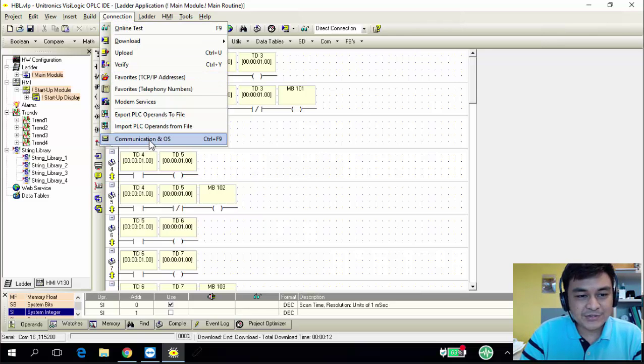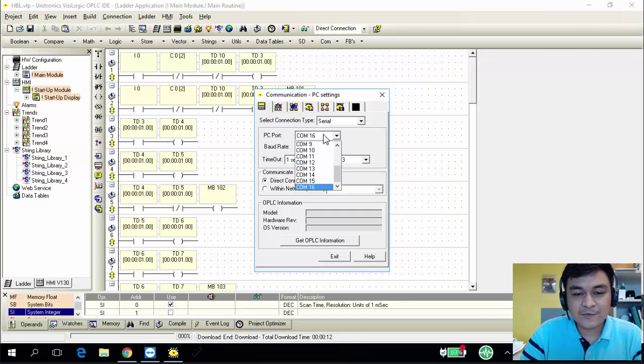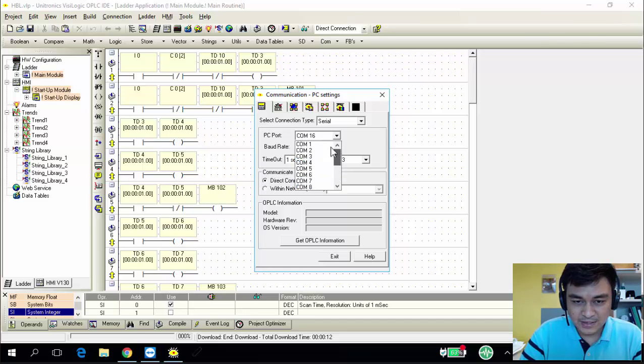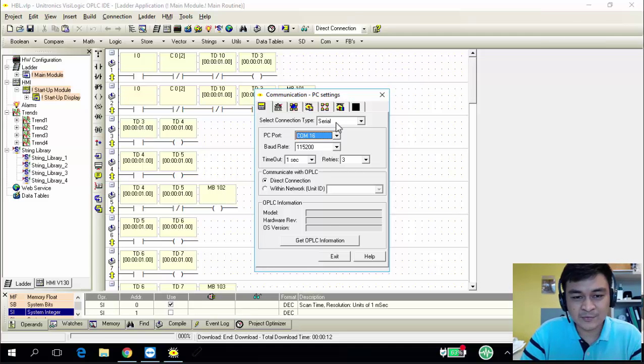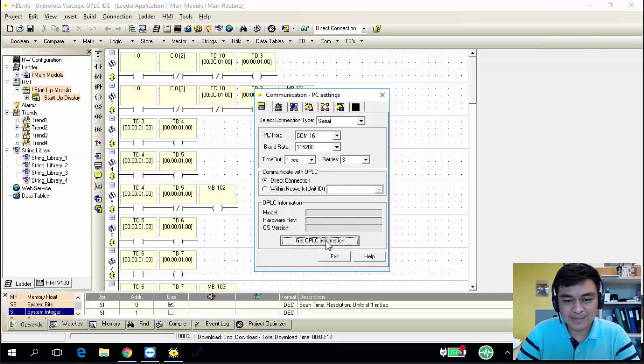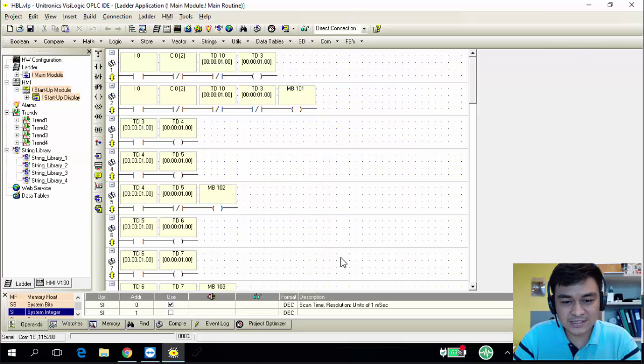Go to Connections, then Communication and OS. For the lab, we are using COM1. For my PC, I'm using COM16 — so there's a slight difference. The baud rate is 115200. We use serial communications. Please check your communications and make sure you can see the OS version, which means your PC is connected to the PLC. After that, just click Exit.